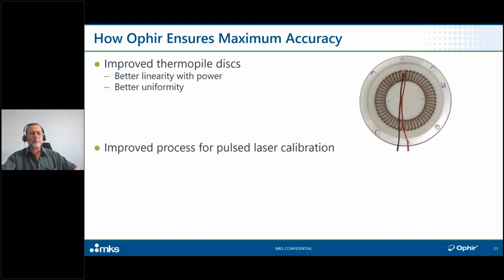Over the years, we've developed an improved process for maximizing the accuracy of the energy per pulse sensors, the pyroelectric sensors, so that the calibration is as independent as possible of pulse-to-pulse instability.